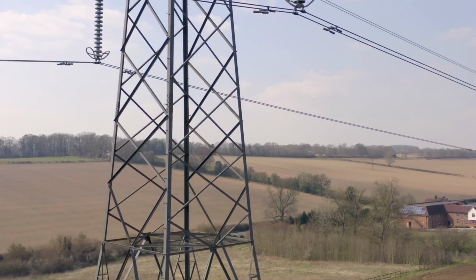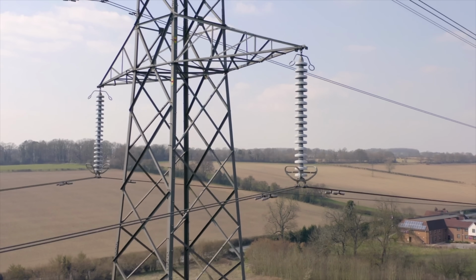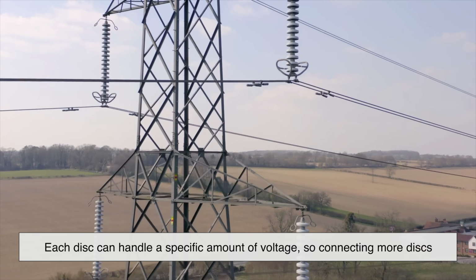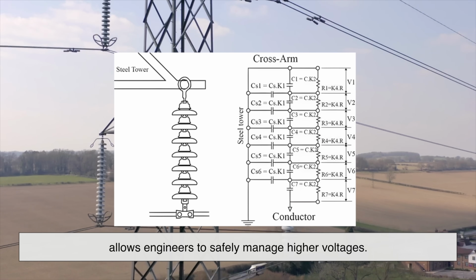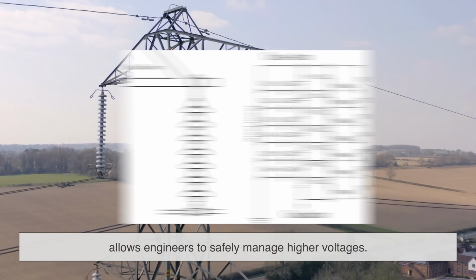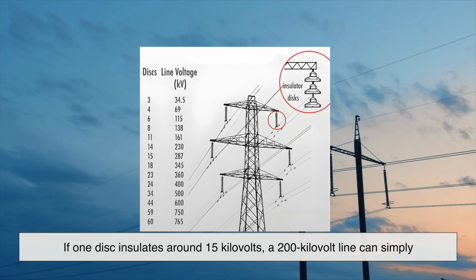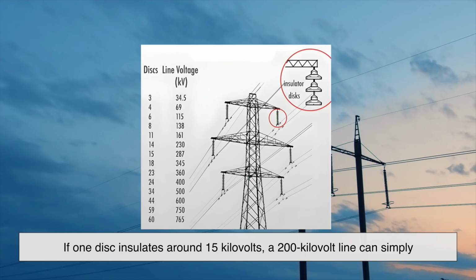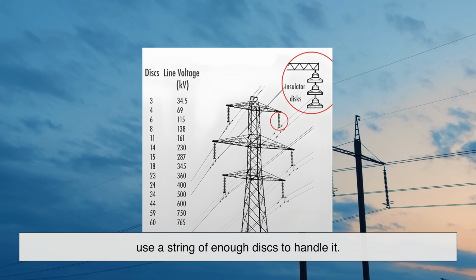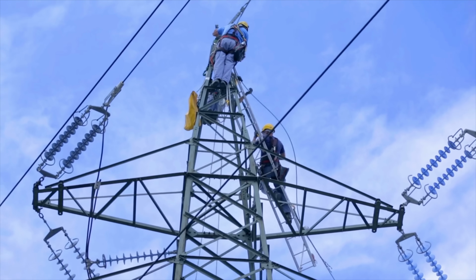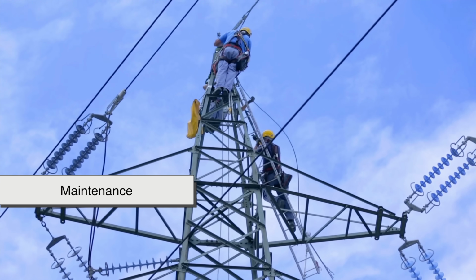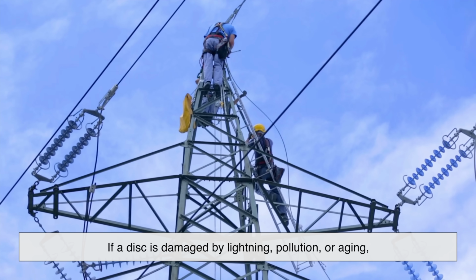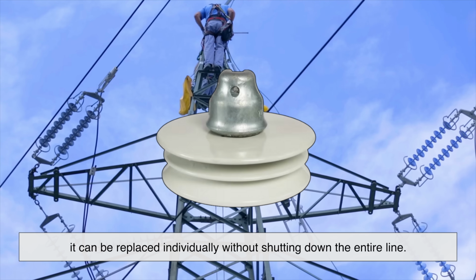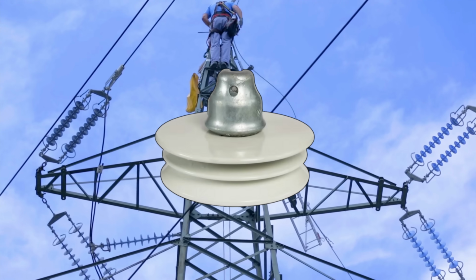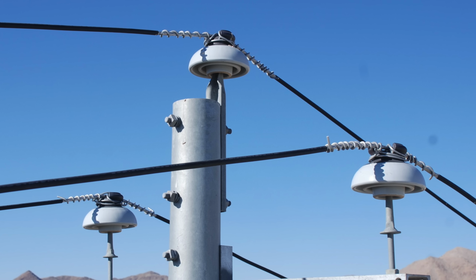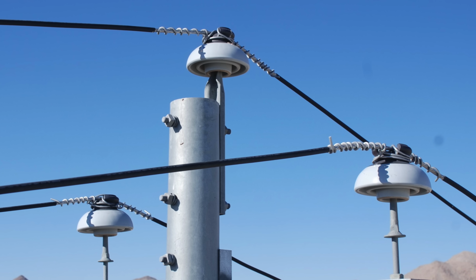It might seem simpler to use one large insulator, but multiple discs offer major advantages. Each disc can handle a specific amount of voltage, so connecting more discs allows engineers to safely manage higher voltages. For example, if one disc insulates around 11 to 15 kilovolts, a 200 kilovolt line can simply use a string of enough discs to handle it. This modular system is also practical for maintenance. If a disc is damaged by lightning, pollution, or aging, it can be replaced individually without shutting down the entire line. A single large insulator would require complete replacement, which is costly and time-consuming.